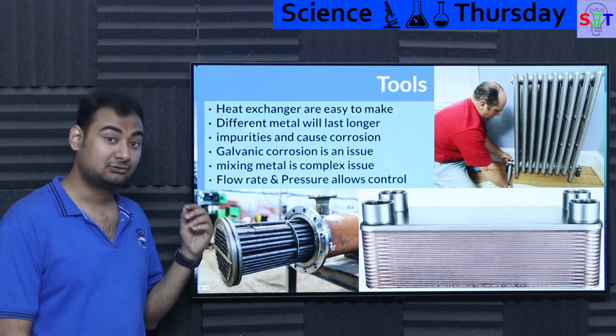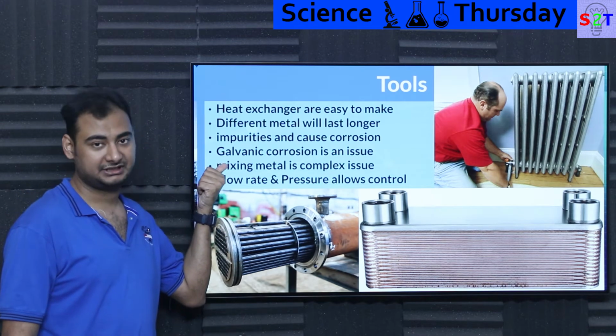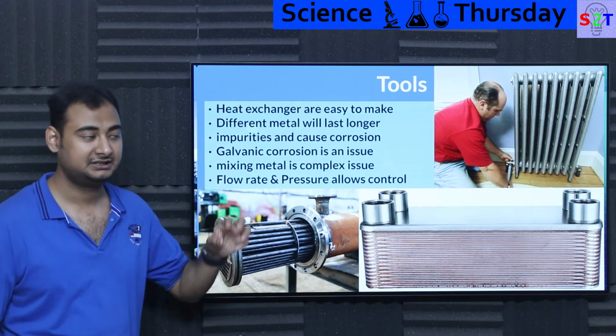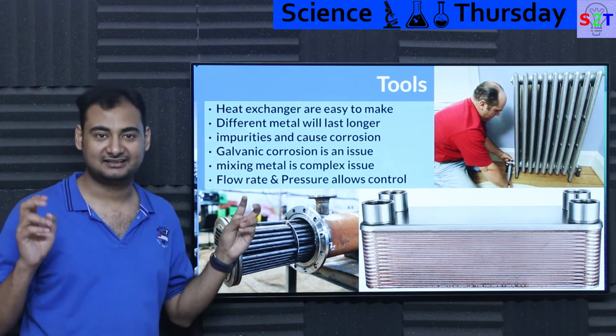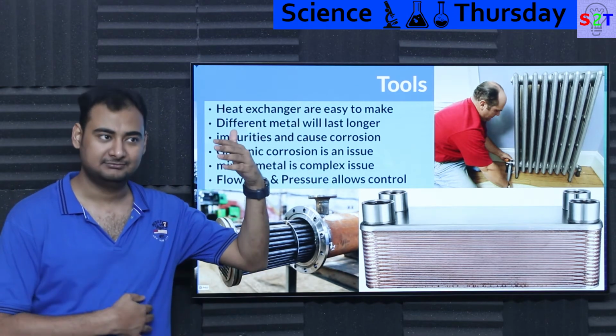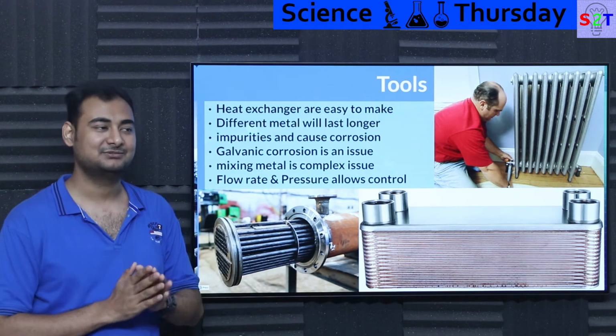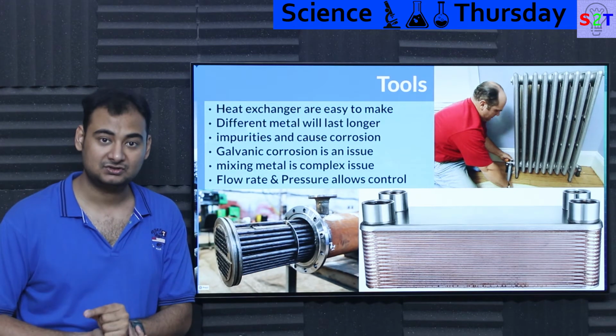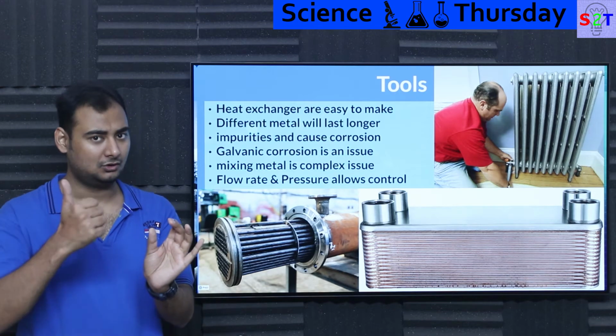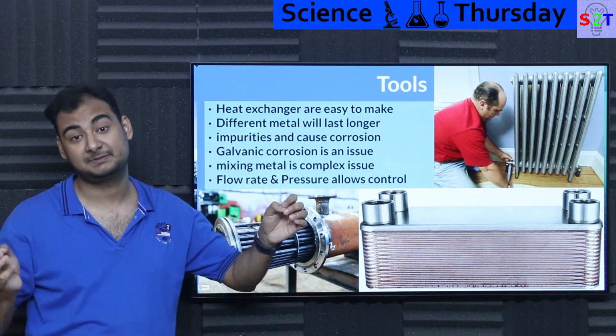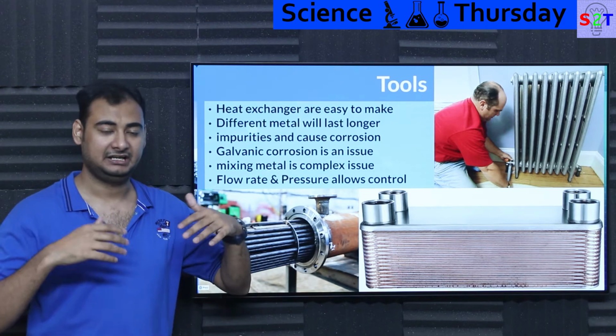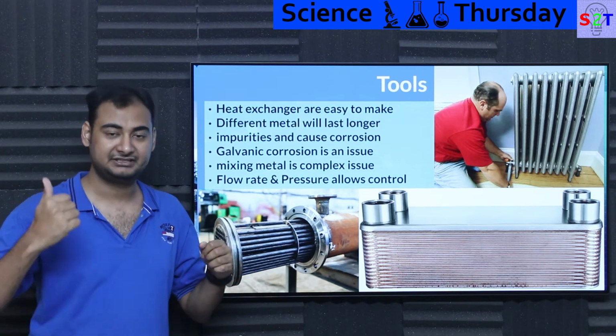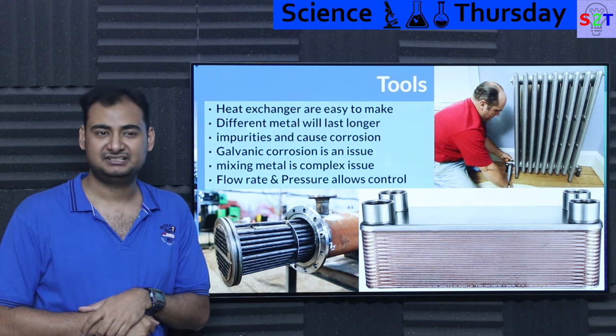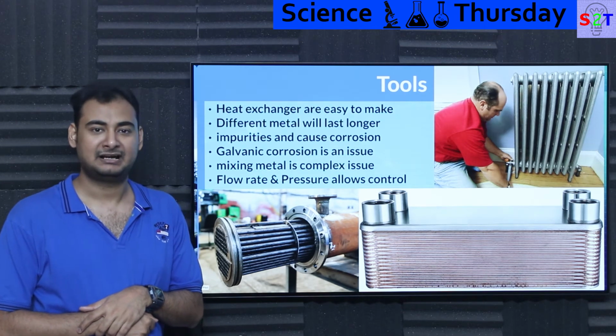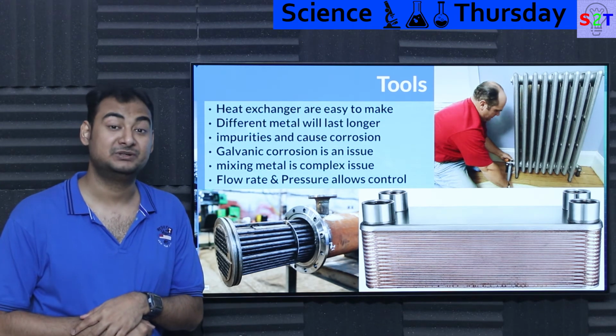Another issue is, because water is conductive, you also have to consider galvanic corrosion. This was a lesson learned by many people long ago, and then the PC community recently, because many times they wanted to use copper blocks for high heat flux CPUs. They wanted copper heat sinks, but copper radiators were expensive, so they thought, what if we use an aluminum radiator? Everything seems fine, everything works, but over time, wait a minute, there's a different color in the water, and randomly your radiator starts to leak because the aluminum corroded.